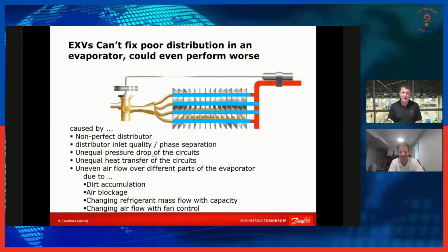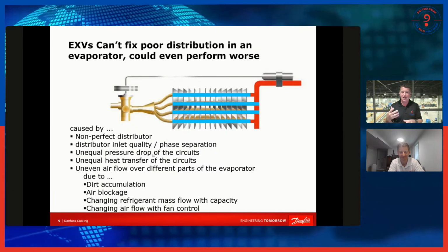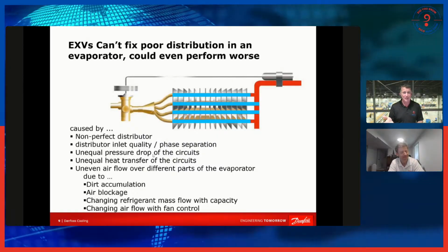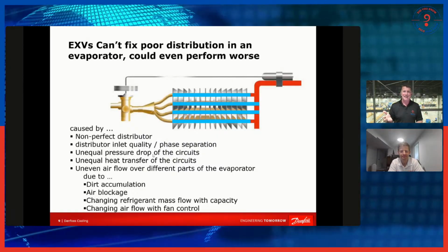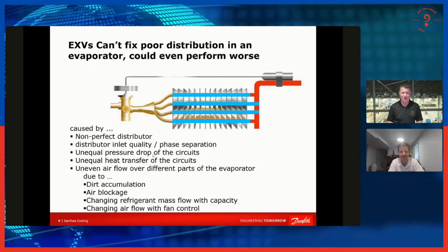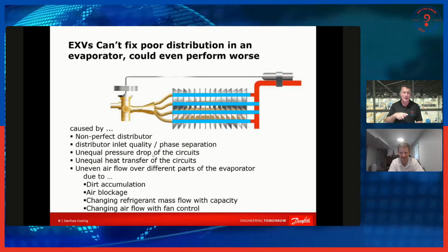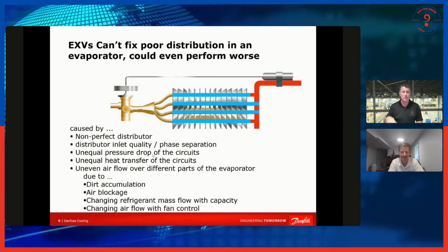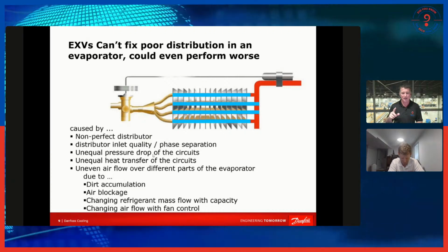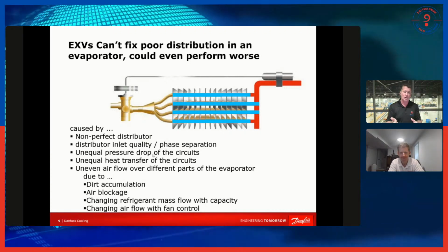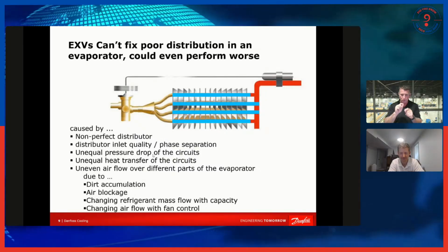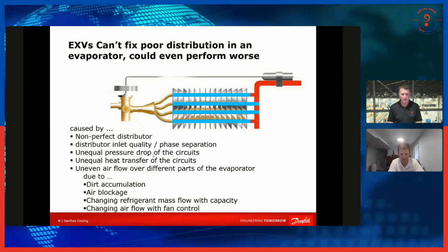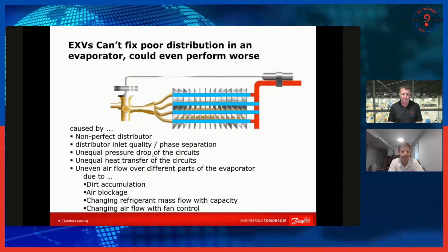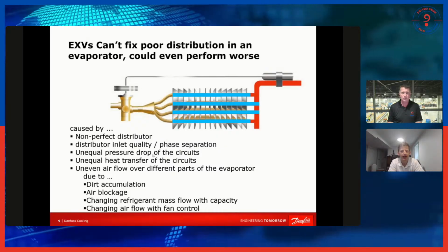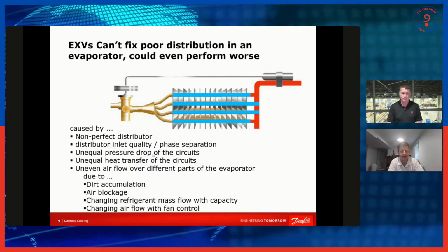And when we do that, now we're completely redistributing air. And if, I shouldn't even say if, I say when the homeowner doesn't redistribute our airflow, we're actually changing the way air is flowing across our coil because we're sending some of that through that bypass line. Mm-hmm. And that will absolutely cause a poor distribution through our separate metering flows. Absolutely. Yeah, I hadn't thought of that example, but that's an excellent one.